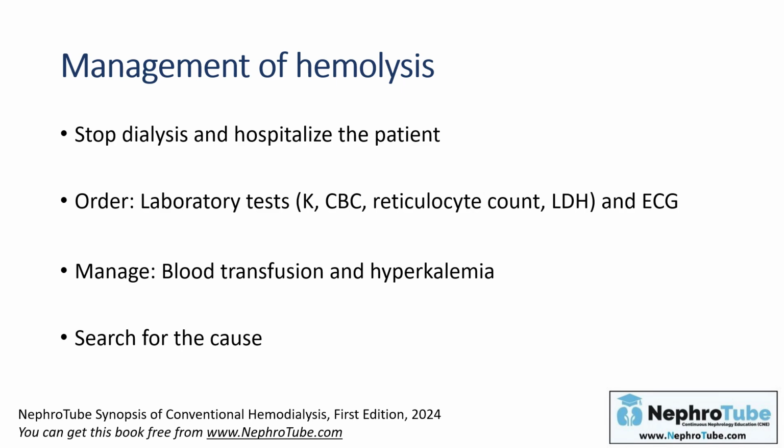And finally, you have to search for the cause of hemolysis, especially checking the dialysate, or especially checking the water treatment unit to be sure that its quality is good and that it forms purified clear water that is used in dialysate, and it must be within the accepted range of chloramine, chlorine, copper, or nitrate in the dialysis water.